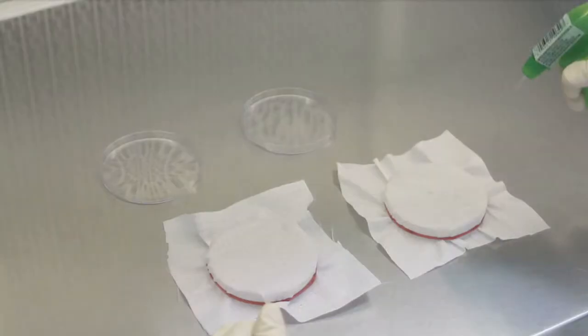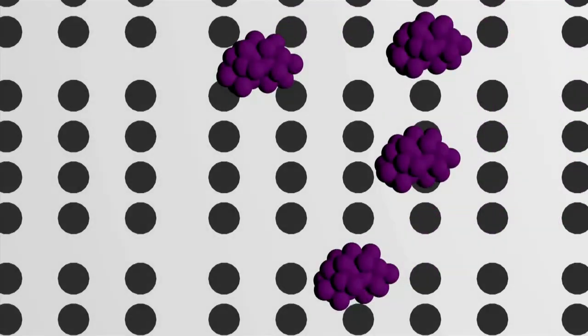The second problem with this test is that it uses a pure culture of Staphylococcus bacteria suspended in a liquid to challenge the fabric. Some individual bacteria can enter the pores and pass through the fabric. However, most of the bacteria will occur in clusters which are too large to pass through the fabric, artificially increasing the BFE.